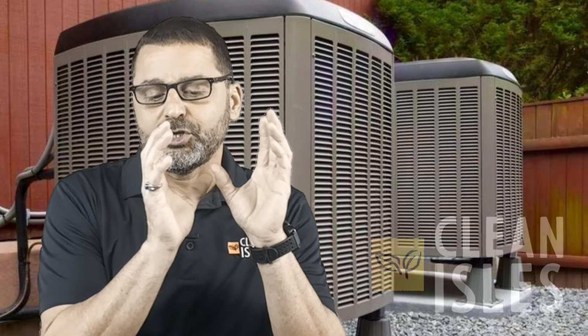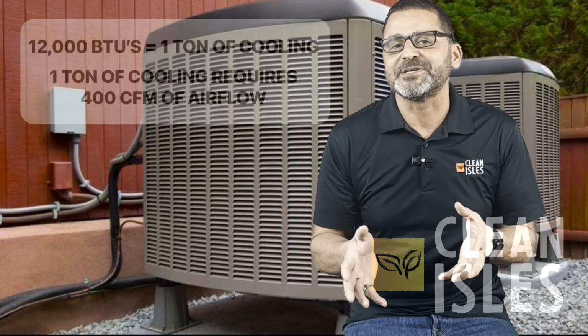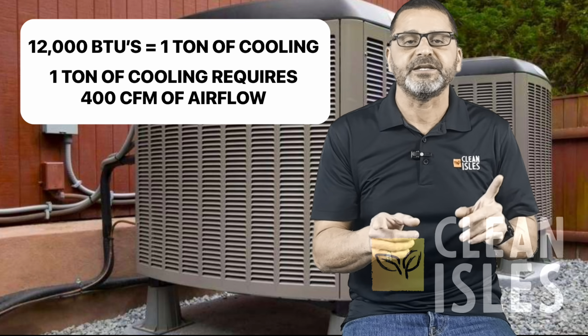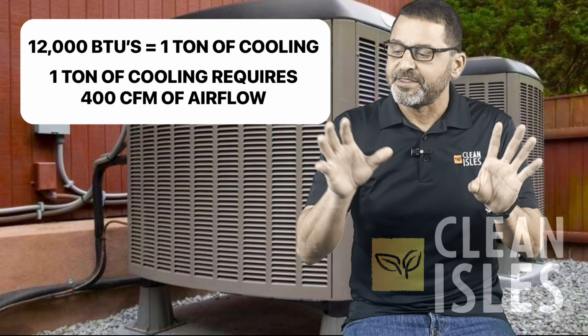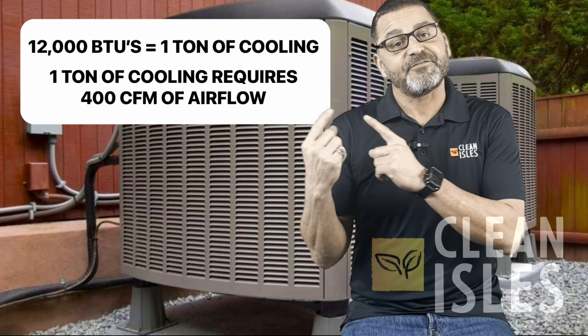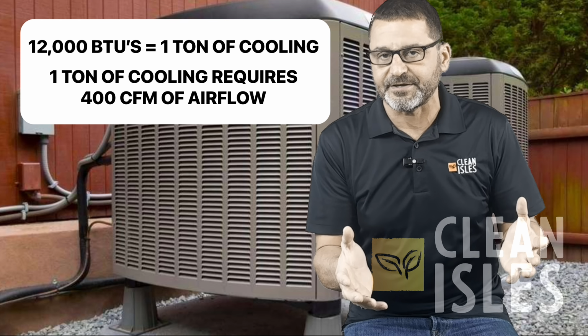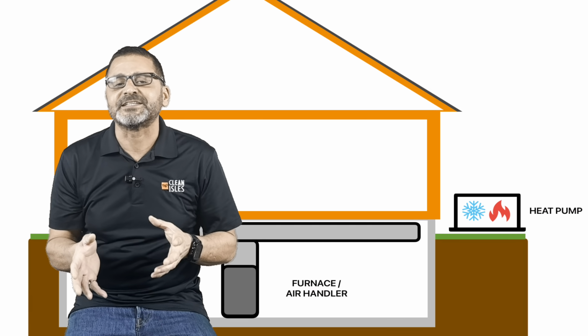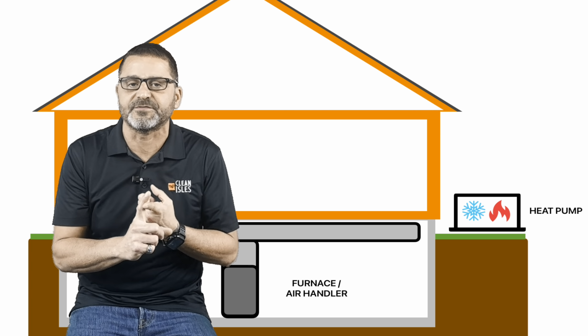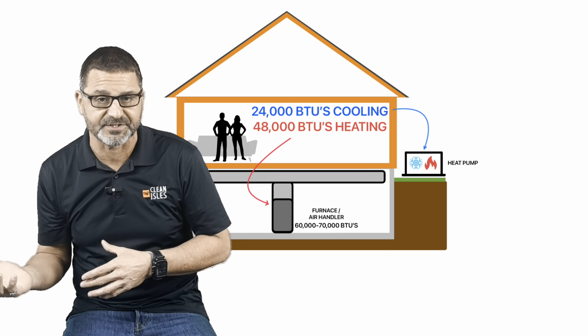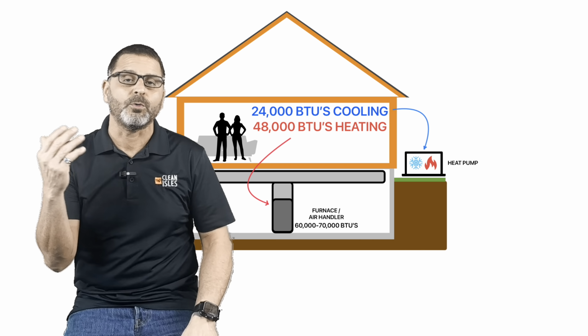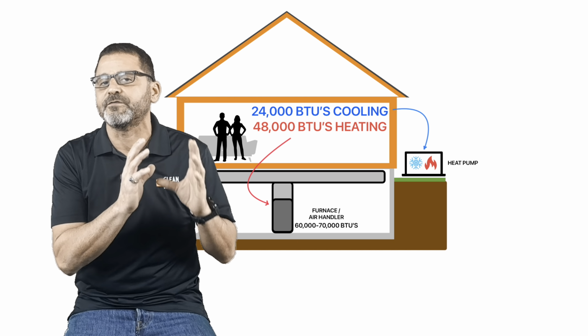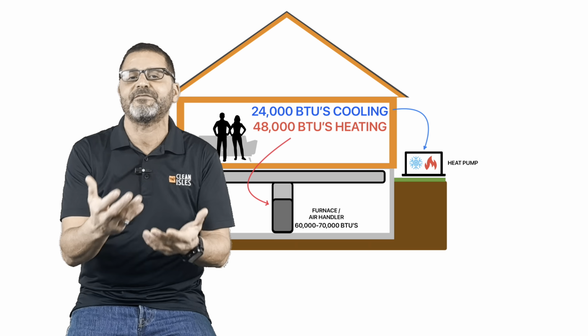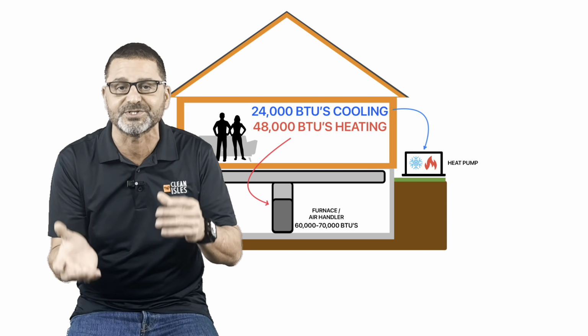In order to understand your heat pump application, you need to realize the basic math. And it's a little bit complicated, so stay with me. So ductwork is always designed on the cooling side, meaning if you need 12,000 BTUs of cooling, that means that you have 1 ton of cooling. If you have 1 ton of cooling, you need 400 CFM of airflow. Knowing if an existing house needs 24,000 BTUs of cooling, it obviously needs 48,000 BTUs of heating. In this example, that's what we have. We have a 2-ton air conditioner and we require 48,000 BTUs of heating, meaning that they probably have a furnace in there about 60 to 70,000 BTUs to cover it.